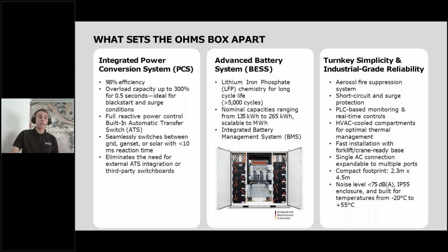It has an overload capacity of over 300%, meaning it's perfect for black starts. It uses lithium iron phosphate batteries for a very long life cycle. It can be scaled from 135 kilowatt hours up to 265 kilowatt hours per unit, so if you put multiple OHMS boxes next to each other, you can scale up to megawatt systems, which I have an example of in a second. It also has an integrated battery management system, the off-grid controller, which is also an in-house creation.